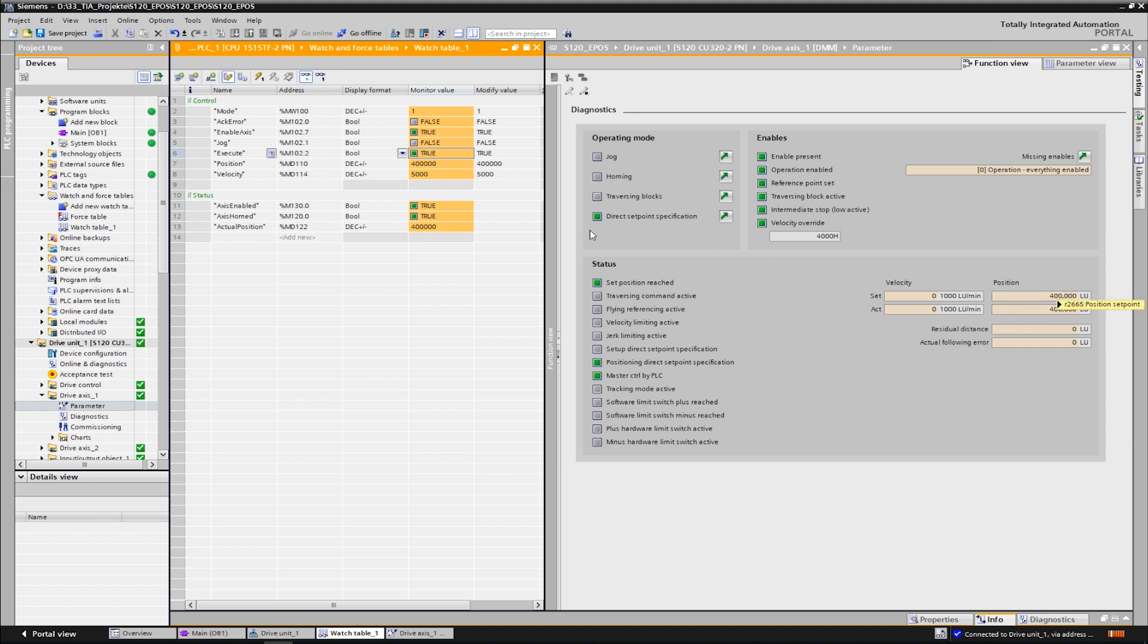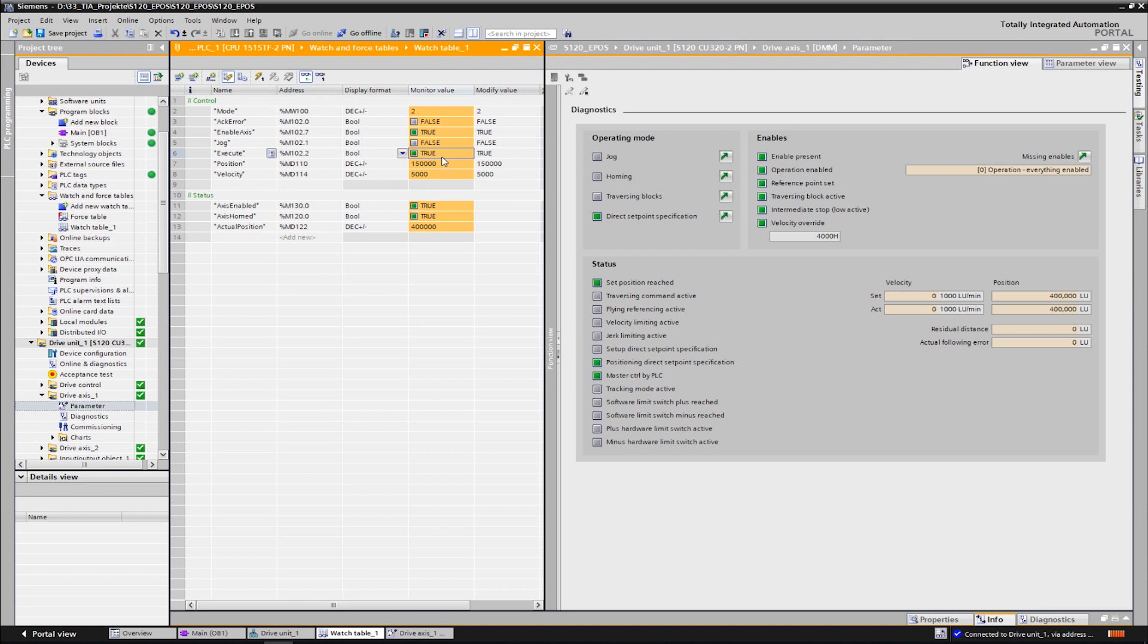We proceed with absolute positioning in the same way. We choose mode 2 and set the set point position to 150,000 LU, which stands for 150 millimeters. We start again with execute and we can see that the axis now moves absolutely to the specified position.